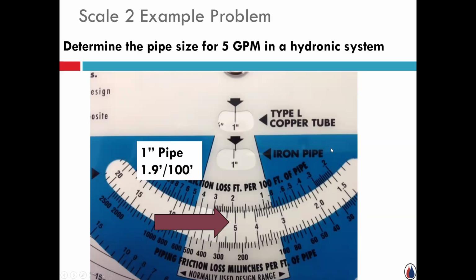Okay, it's telling me that flow rate of 5 GPM through that 1-inch pipe will offer 1.9 feet of pressure drop, in feet of head, for every 100 feet of pipe.